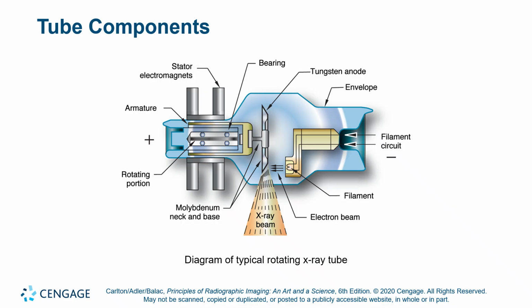But here's our modern X-ray tube, very similar to the Coolidge tube that you see. So it's got the same basic components. It needs a cathode and an anode. The nuance, I guess, is that the anode rotates. That's the only difference between this and a Coolidge, an original 1911 patent Coolidge tube. The Coolidge tube might also have had a water-cooled anode. Some designs indicate that.